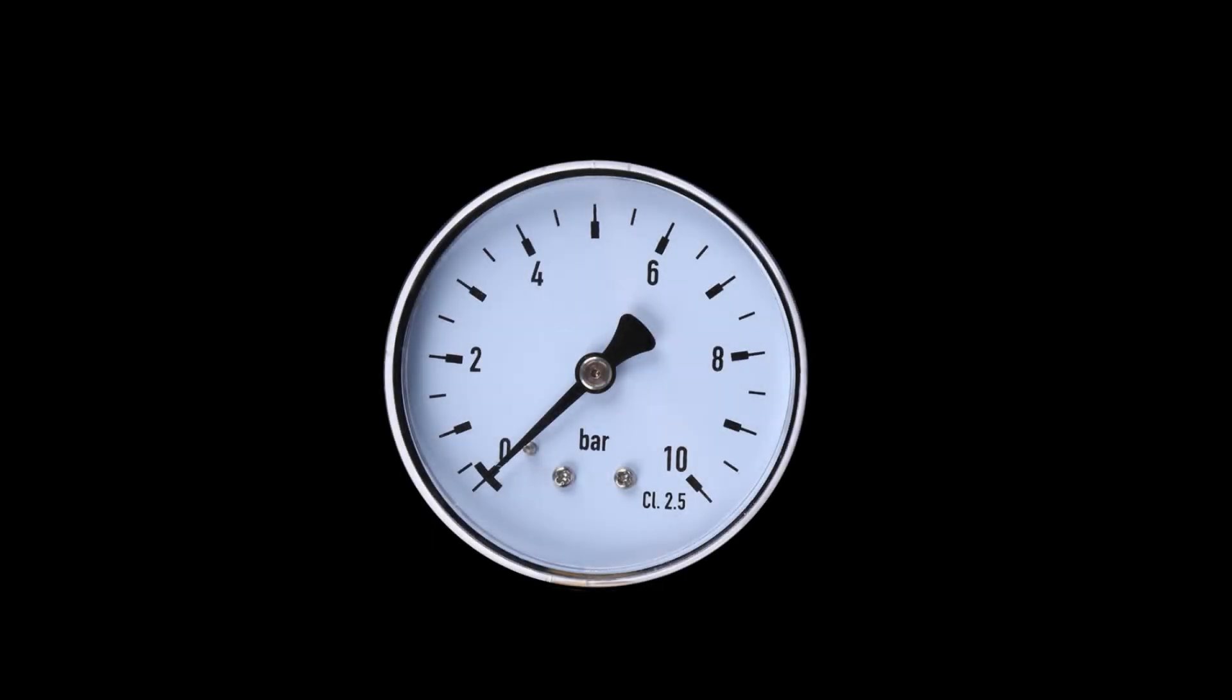So let's see these values. Zero pressure usually means not enough water, the trickle on the tap, if anything at all. The minimum pressure anywhere, at any moment, in the system is 10 meters or 1 bar. Sometimes we need to depressurize a pipe in a very specific location, but let's forget about that for now.